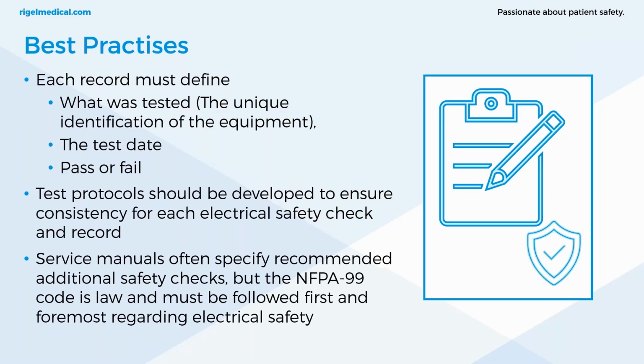It's always worth looking at even what the manufacturer recommends, and look at what they've stated in their own service manual, and always looking at that for their guidance. And as it states here at the bottom, service manuals may specify additional checks, but the NFPA 99 code is law and must be followed first and foremost regarding electrical safety.